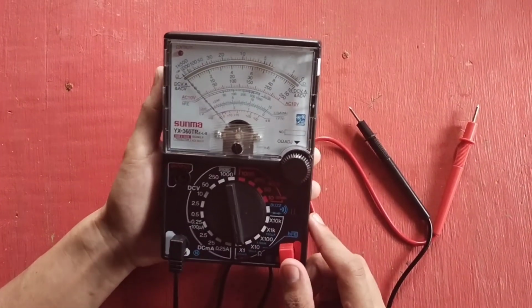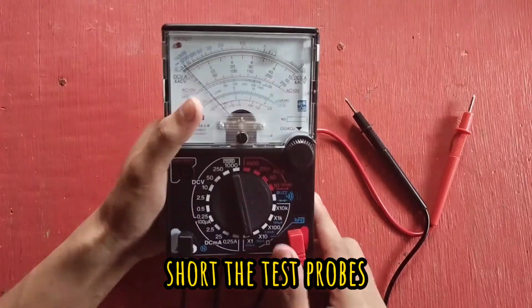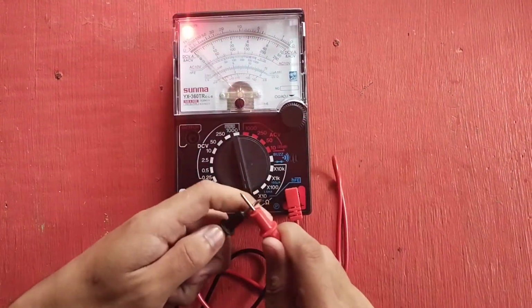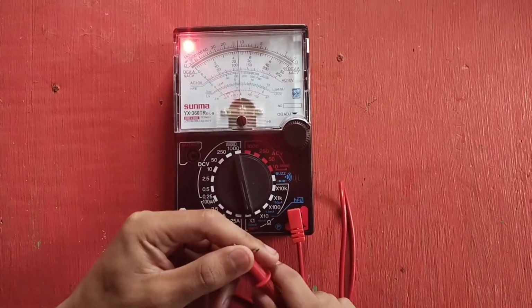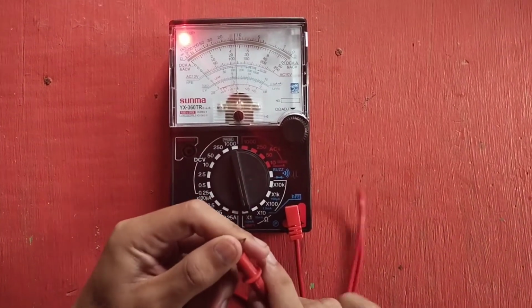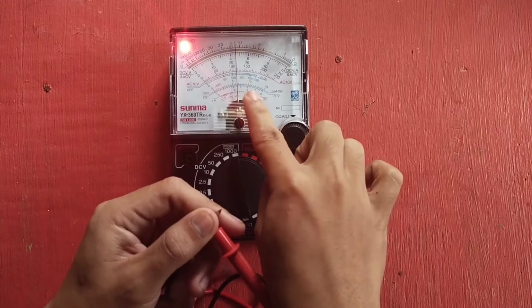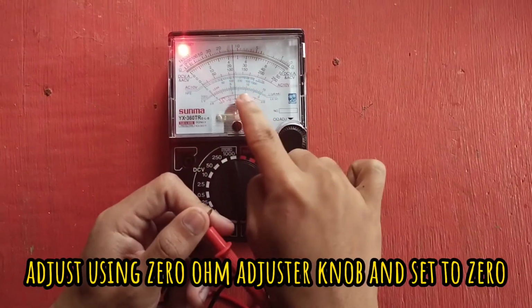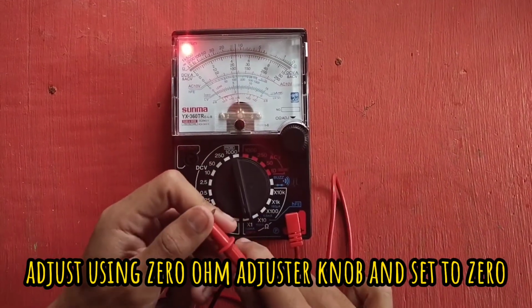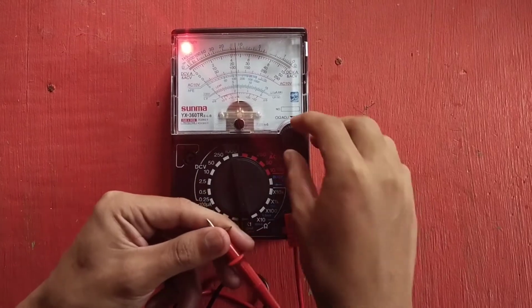Then, to start calibrating, short the test probes together. The pointer must point to the 0 scale. If not, like this one, you need to adjust it using the 0 ohm adjuster knob until it points to 0.